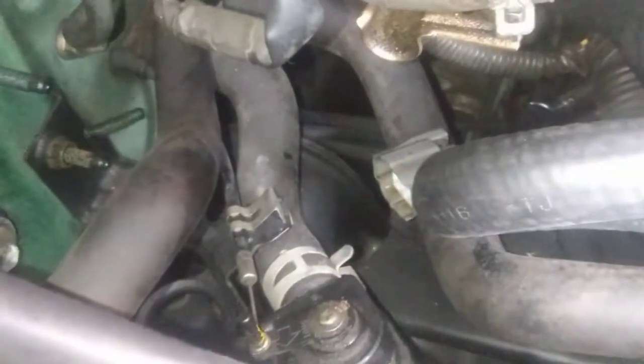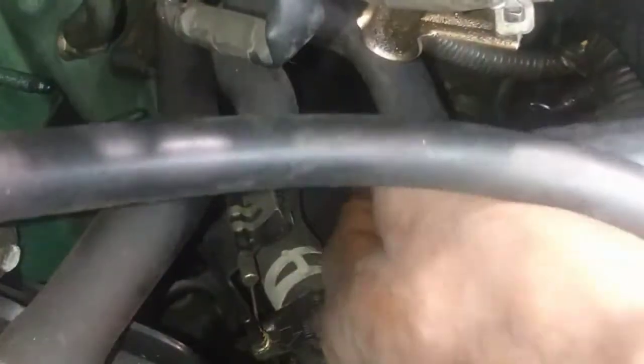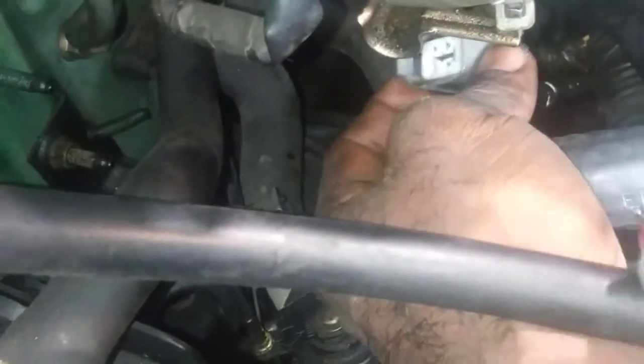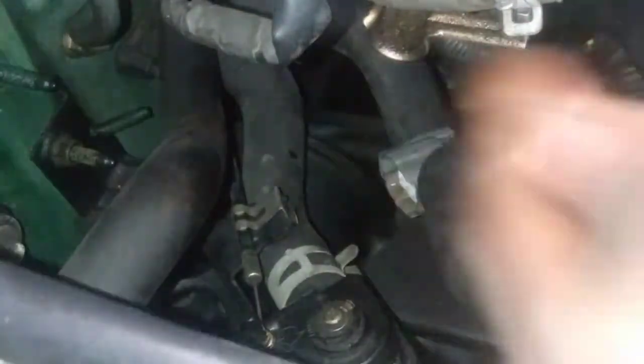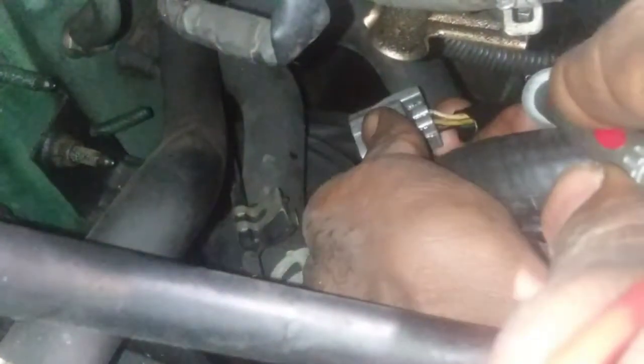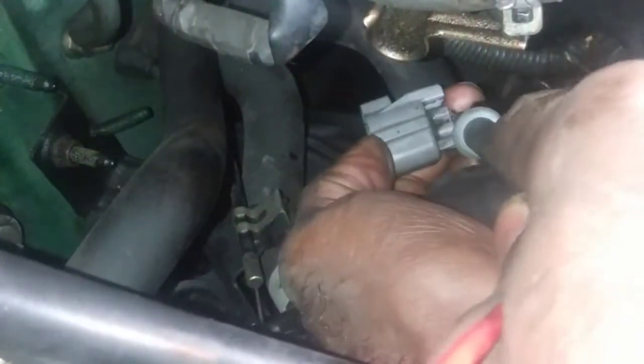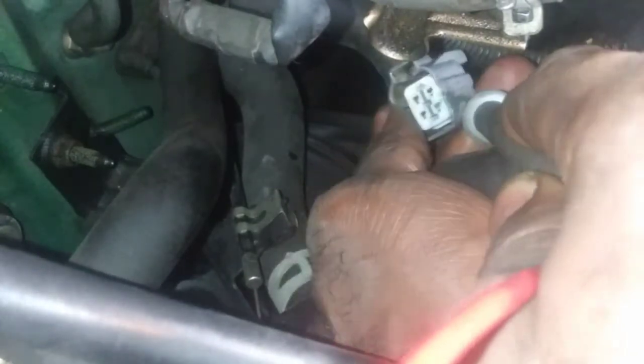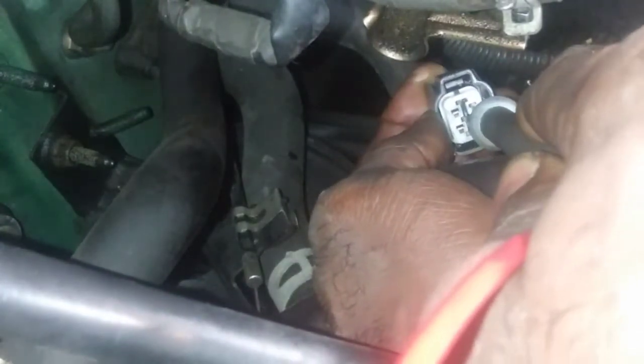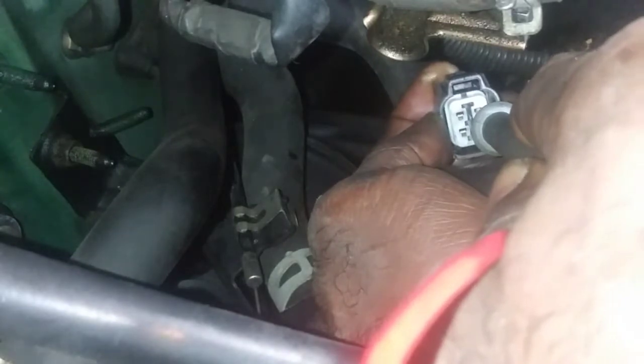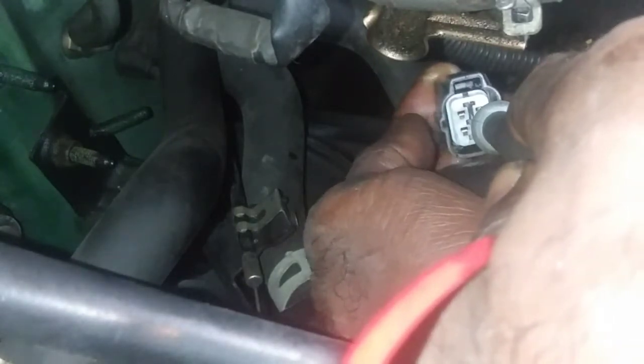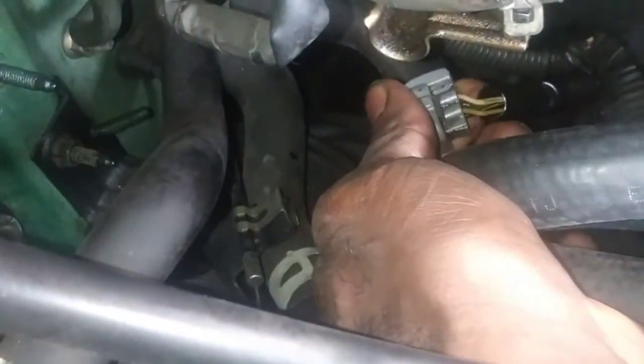So I got my voltmeter here. My black wire is grounded, and I'm going to jump right onto that white wire, if I can get to it without blocking the camera, and see if we got our 1.275 or over 1 volt value. And wow, I got 11 volts. I got battery voltage on that white wire.